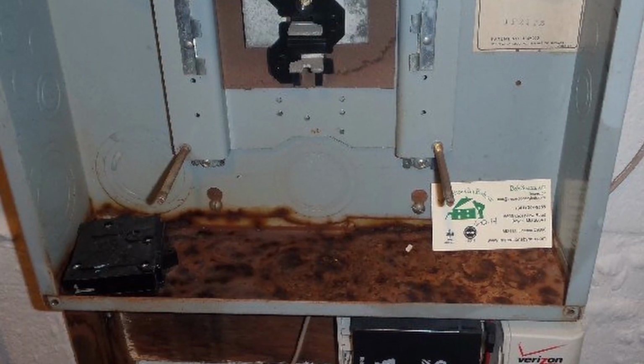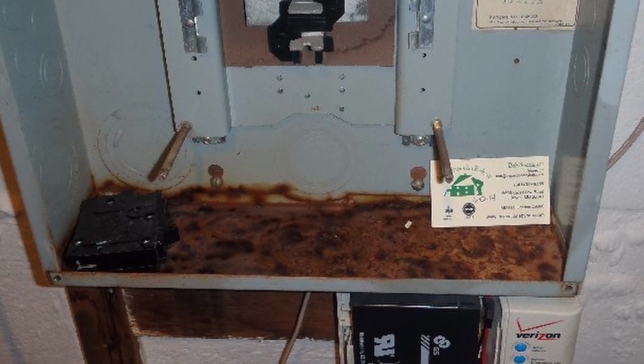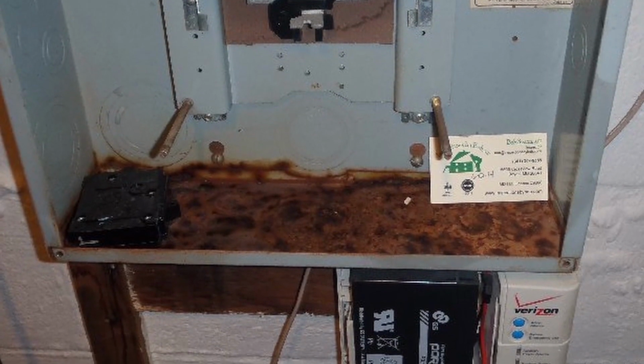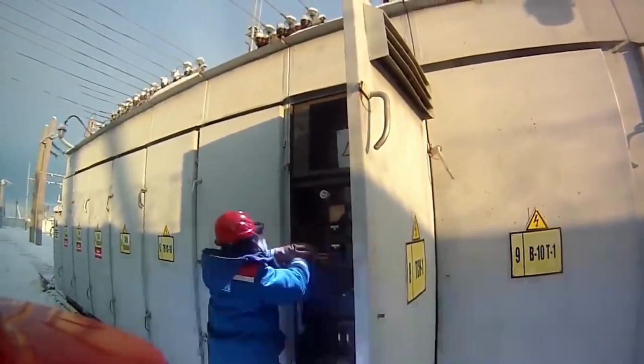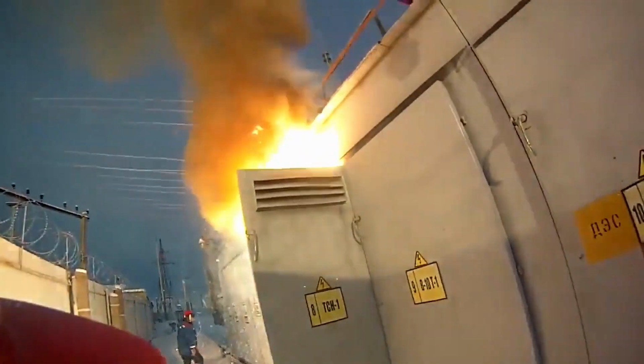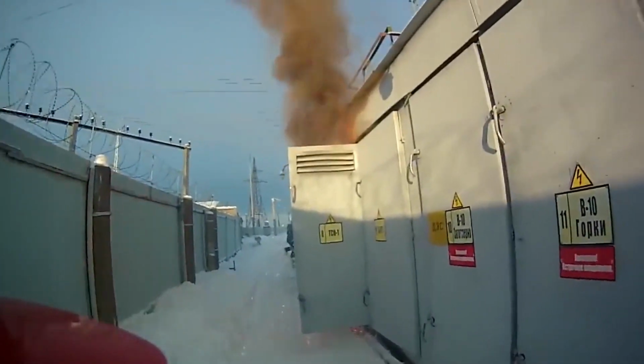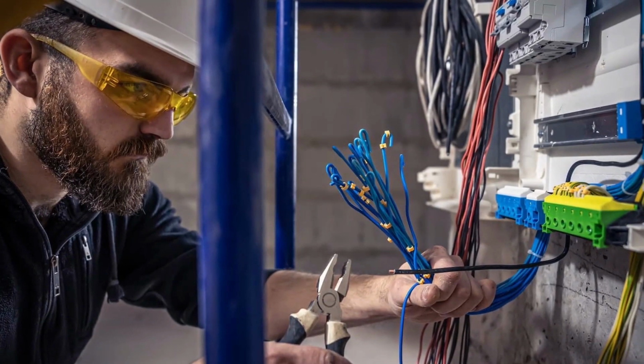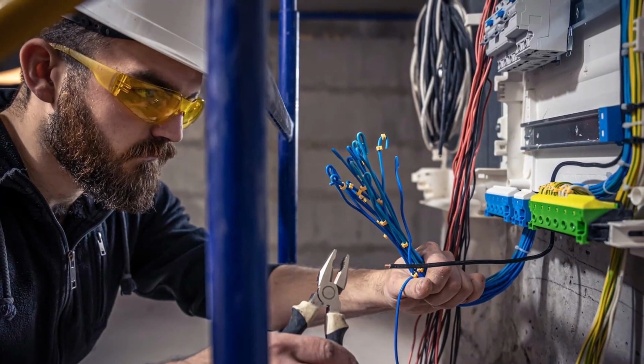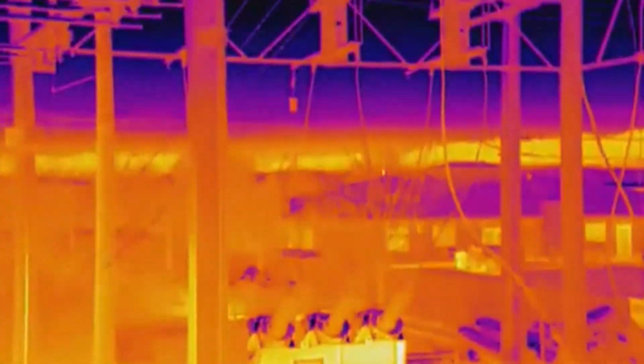Mechanical degradations, such as looseness, corrosion or cracks, can reduce reliability and efficiency of electrical equipment. Insulation issues, such as leaks or damage, can increase the risk of electrical shocks and outages. Loose connections can reduce the efficiency of electrical equipment. Overloading of electrical equipment can cause overheating and damage to the equipment. Autonomous devices equipped with thermal imaging sensors can detect overheating by measuring the temperature of the equipment and identify other potential safety hazards.